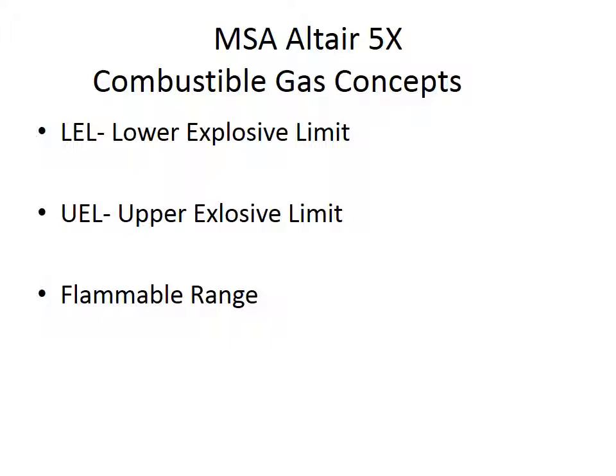An important thing to note is that when you're over the UEL, you're not necessarily in a safe environment. Through ventilation or just dissipation of that gas over time, the mixture in the air can come back down below the UEL into the flammable range. So that's something you've got to be aware of: when you're up over the UEL, you can still get back down into the danger zone. We'll talk about how the meter is going to react to that situation in a couple of minutes.